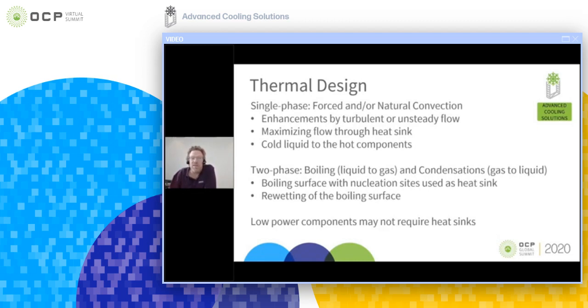To improve the effectiveness of a heat sink, it should be designed for immersion by maximizing the flow through the heat sink. Enhanced performance will be achieved by getting colder liquid to the hot components as well. Further heating enhancements can be achieved by increasing flow rate from a laminar flow to turbulent. So a laminar flow builds up thick thermal boundary layers, which reduces the thermal performance. These boundary layers can be reduced by increasing the flow rate and achieving a turbulent flow. However, with the relatively high viscosity of immersion liquids compared to air, a turbulent flow may not be achievable. And the next best thing is then to create an unsteady flow that can break up the boundary layers and enhance the thermal performance compared to laminar flow.